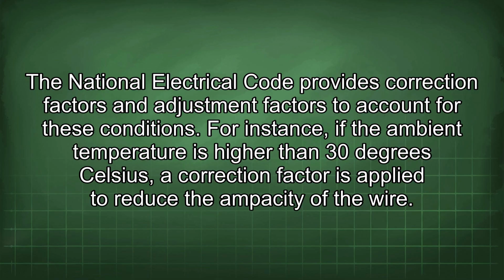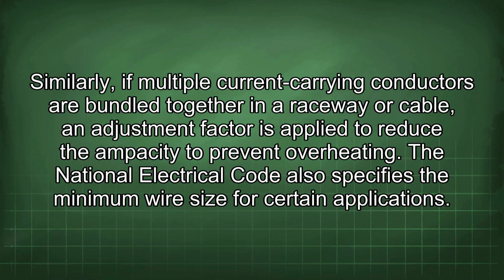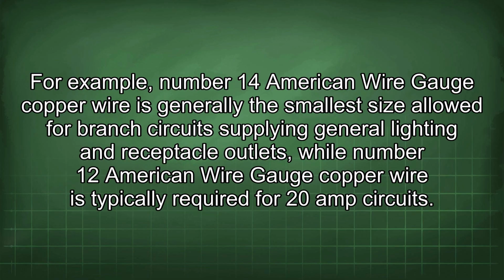For instance, if the ambient temperature is higher than 30°C, a correction factor is applied to reduce the ampacity of the wire. Similarly, if multiple current-carrying conductors are bundled together in a raceway or cable, an adjustment factor is applied to reduce the ampacity to prevent overheating. The National Electrical Code also specifies the minimum wire size for certain applications. For example, number 14 American wire gauge copper wire is generally the smallest size allowed for branch circuits supplying general lighting and receptacle outlets, while number 12 American wire gauge copper wire is typically required for 20 amp circuits.